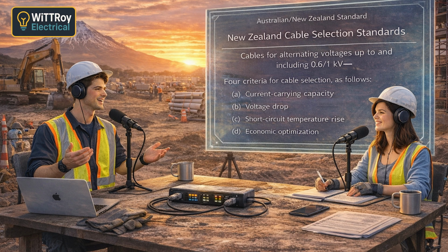Correct. And if it's too high, we increase cable size. Yes. So bigger cable means less resistance. Exactly. So less voltage drop. So even if current is okay, voltage drop can fail. Yes, and that's a very common exam mistake. Okay, that's clearer now. Good.